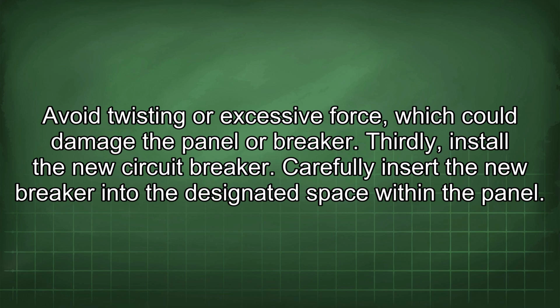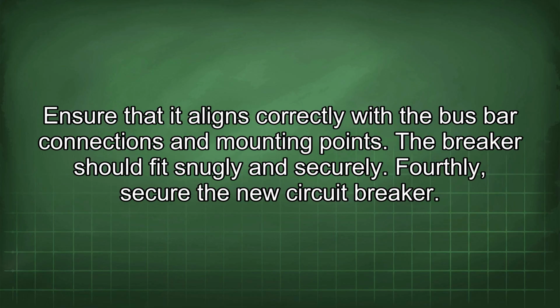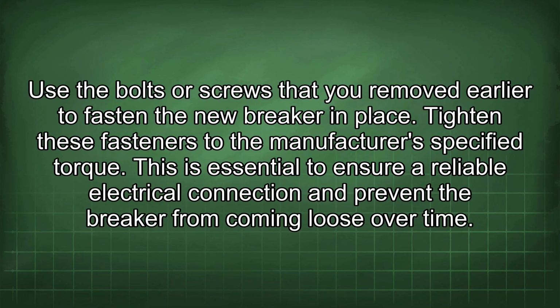Thirdly, install the new circuit breaker. Carefully insert the new breaker into the designated space within the panel. Ensure that it aligns correctly with the bus bar connections and mounting points. The breaker should fit snugly and securely. Fourthly, secure the new circuit breaker. Use the bolts or screws that you removed earlier to fasten the new breaker in place. Tighten these fasteners to the manufacturer's specified torque. This is essential to ensure a reliable electrical connection and prevent the breaker from coming loose over time.